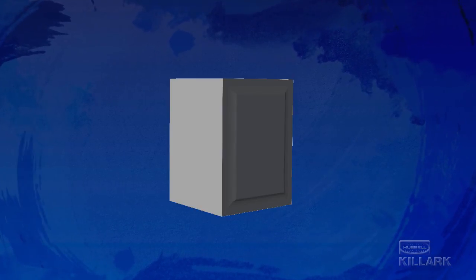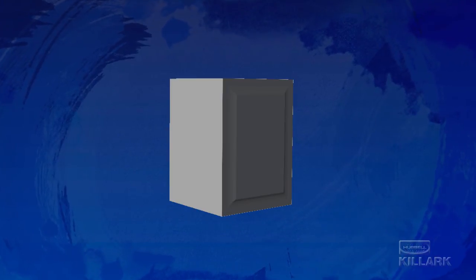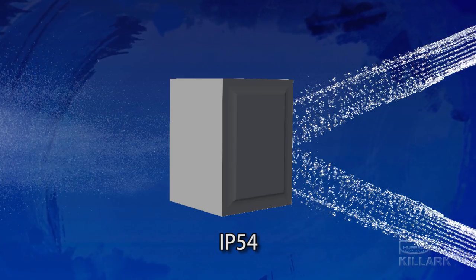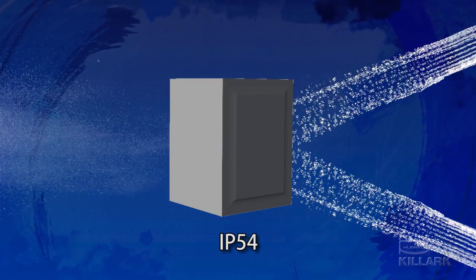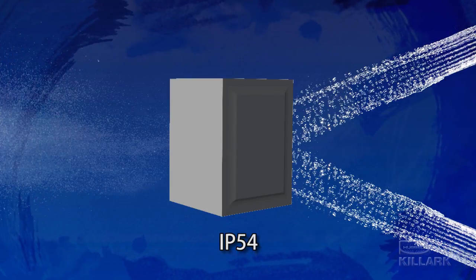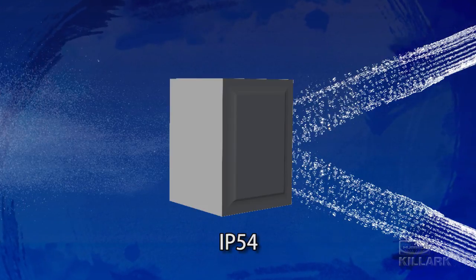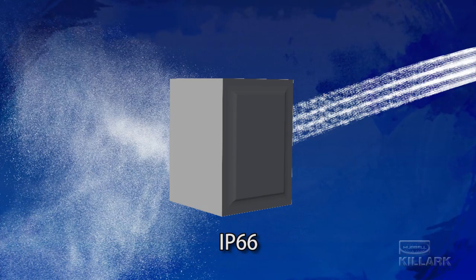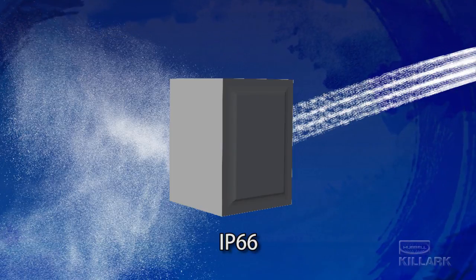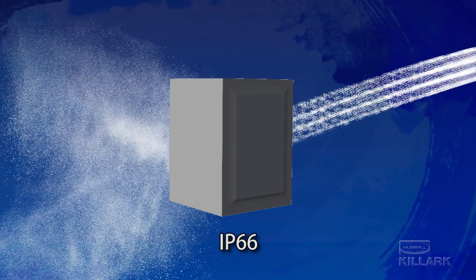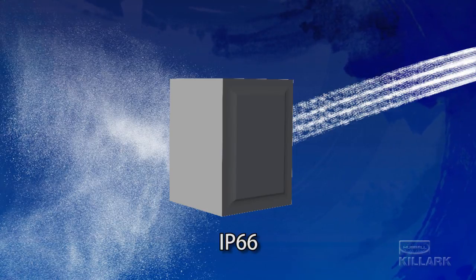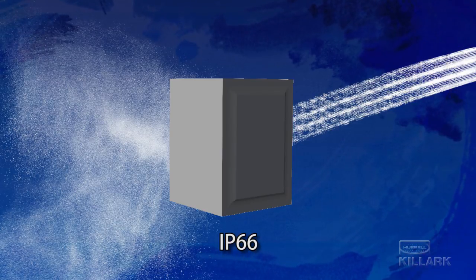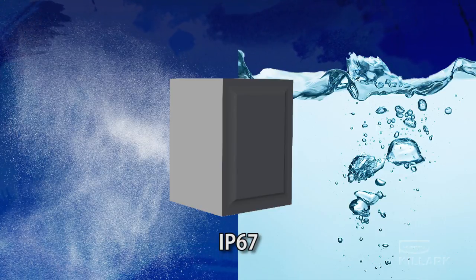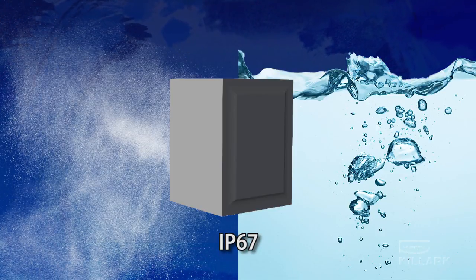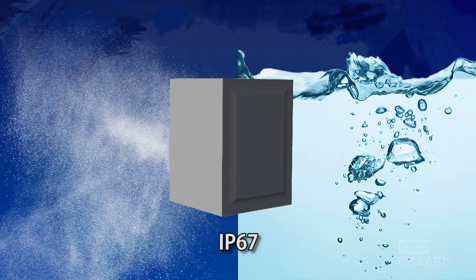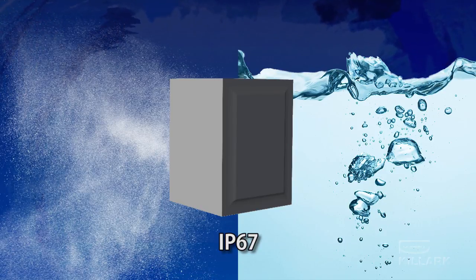Examples of typical ingress protection ratings would be IP54, for an enclosure that is protected from dust as well as water splashing from any direction, neither of which could enter in a sufficient amount to cause harm. An IP66 rating would mean that the enclosure would allow no dust to enter. It is fully dust-tight, and powerful water jets or heavy seas would have no effect. If the rating were raised to IP67, the enclosure would also be able to protect the equipment from immersion in shallow water for a short period of time, less than 30 minutes.